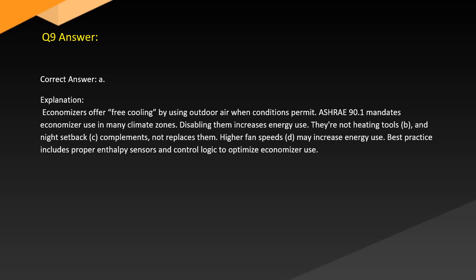Answer. Correct answer: A. Explanation. Economizers offer free cooling by using outdoor air when conditions permit. ASHRAE 90.1 mandates economizer use in many climate zones. Disabling them increases energy use. They're not heating tools (B). A night setback (C) complements, not replaces, them. Higher fan speeds (D) may increase energy use. Best practice includes proper enthalpy sensors and control logic to optimize economizer use.